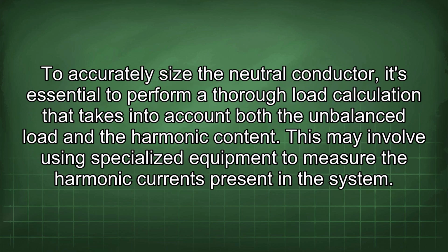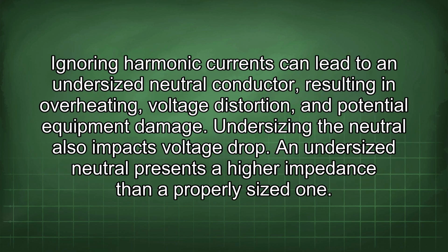To accurately size the neutral conductor, it is essential to perform a thorough load calculation that takes into account both the unbalanced load and the harmonic content. This may involve using specialized equipment to measure the harmonic currents present in the system. Ignoring harmonic currents can lead to an undersized neutral conductor, resulting in overheating, voltage distortion, and potential equipment damage.